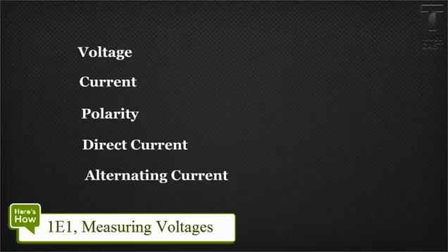With the power supply turned off and the AC/DC voltage adjustment turned fully counterclockwise, insert the test leads into the front panel outlet. Press the 0 to 120 VAC switch to make sure the amp/volt switch is in the voltage position. Turn the power supply on and increase the AC/DC voltage clockwise until the display indicates 115 volts.